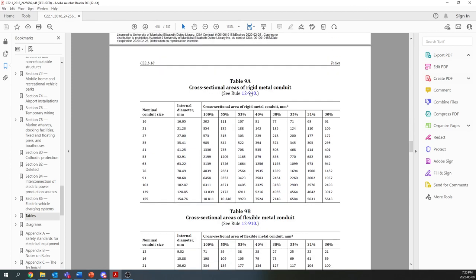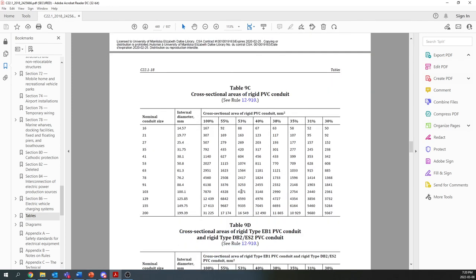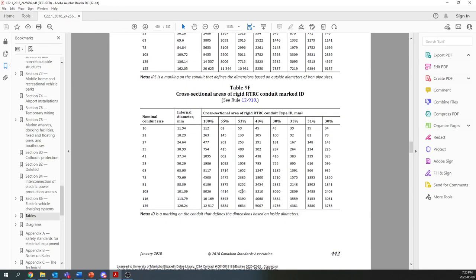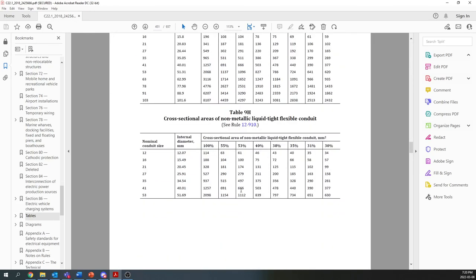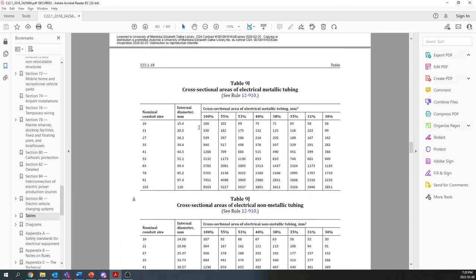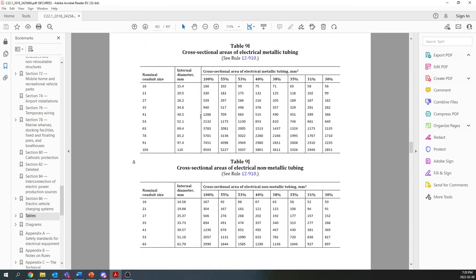Let's pick electrical metallic tubing, or EMT. That's a pretty commonly used conduit in the industry. And we're going to go, here we go. Yes, non-metallic and metallic. I got confused for a second. So we're on the 40% size, and they've actually derated this already for you. They've already taken what's 40% of 100% here. So we can actually look at either 1,000 on this column or 400 on this column. In either case, we're actually going to be using a 41 conduit size.